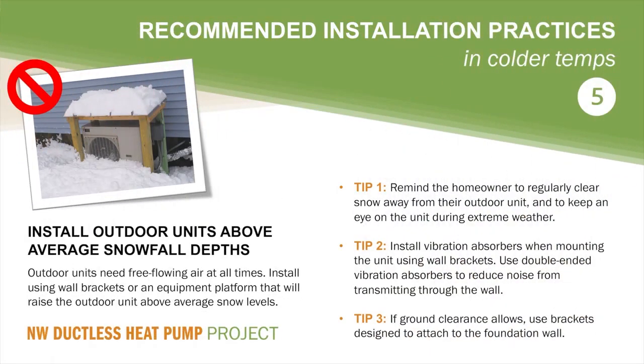The next recommendation is, install outdoor units above average snowfall depths. Outdoor units need free-flowing air at all times, and in areas with high snowfall, it is important to install outdoor units above regular snow depths. This may involve using wall brackets or an equipment stand that will raise the outdoor unit above these typical snow levels. There are a few additional tips we can recommend, and these are to remind the homeowner to regularly clear snow away from their outdoor unit and to keep an eye on the unit during extreme weather.